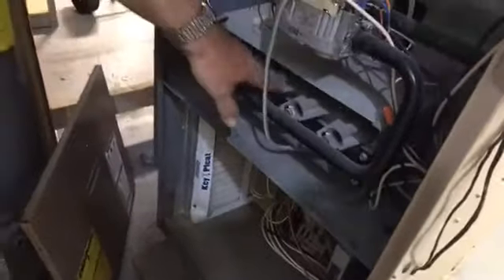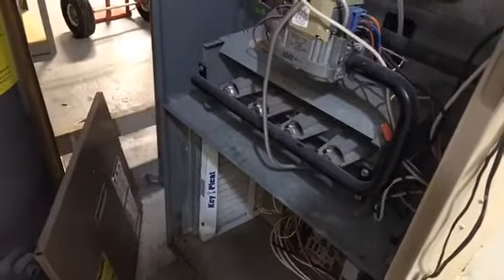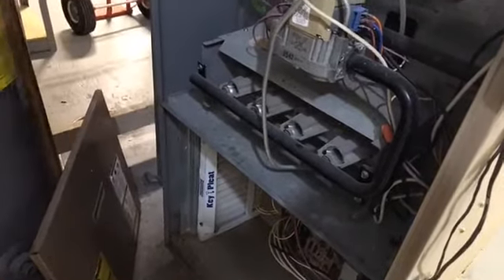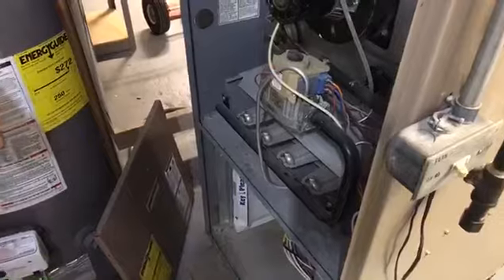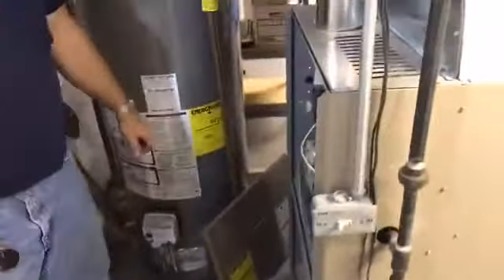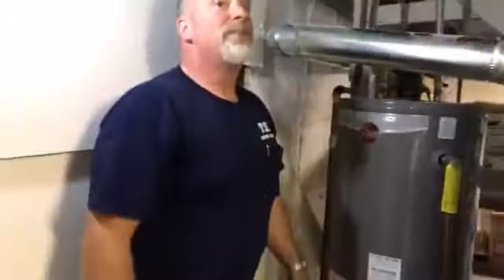So you dive into the... These are your burners, right? The flame's actually at the other end where it goes inside and runs through the heat exchanger, and then all of it's drawn out through the exhaust here. Okay. Now, one of the things that came up when you inspected mine was that there was a cracked heat exchanger. Yes. And luckily mine was one that could be replaced. Some of them can't without replacing the whole furnace. Older furnaces, anything older than 20 years old, is pretty much right.